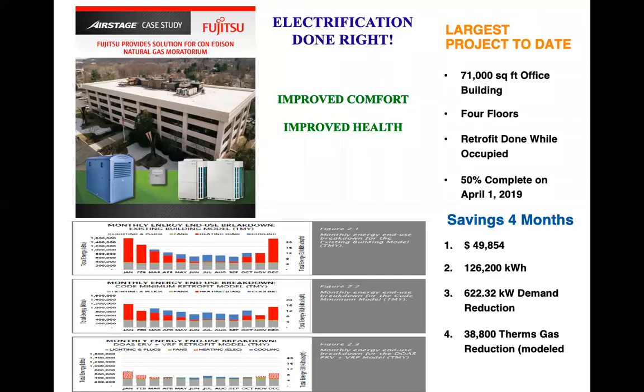What the middle graph depicts is modeled what the results would have been if we had replaced the existing equipment with code compliant equipment. So replacing that rooftop equipment with new rooftop equipment. And you can see savings, not insignificant, but not anywhere near what you see on the bottom graph, which was modeled for our retrofit with heat pumps and very high efficiency heat recovery ventilation. And we've actually exceeded that model fairly significantly.